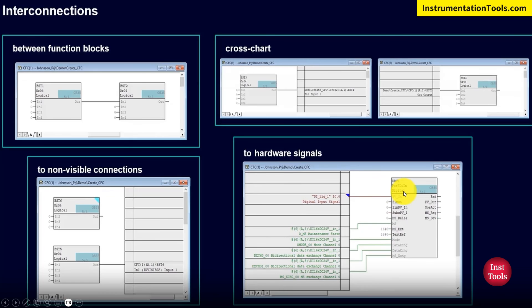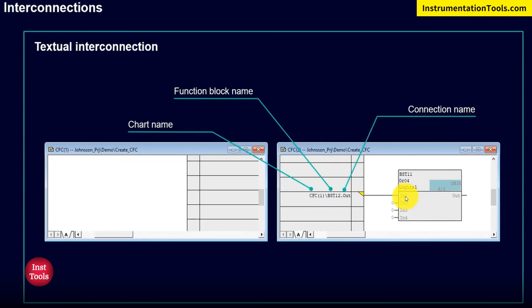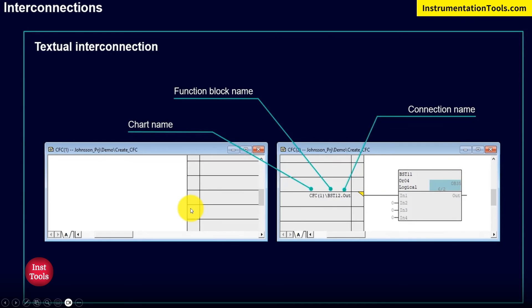Fourth, FB block connection to hardware signals: as mentioned, the CFC directly takes inputs from I/Os. The hardware signals are represented with a notation like 'PV_IN', which takes data from the corresponding I/O such as I0.1 and processes the signal. Fifth, textual interconnection: if a block is not yet available but will be derived in the future, we can create a textual interconnection using a local mark placeholder. Once the block is declared in the future, it will automatically connect to the corresponding block we defined.